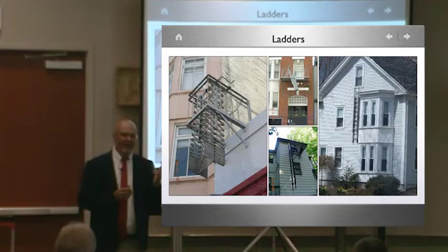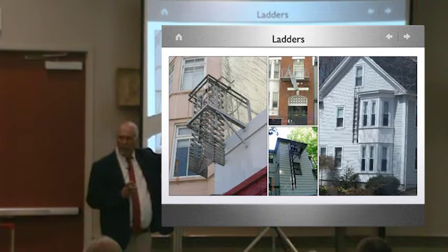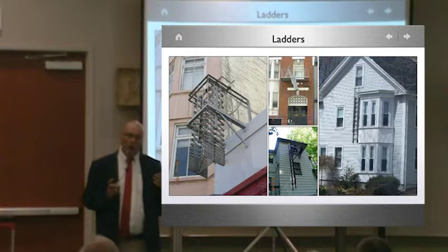Allowed, right? So here's the thing. You have to have a balcony outside your window so you can prepare yourself to use a ladder. These showed up on Saturday or Sunday, these ladders. Okay, guys? So my question always to the city official is, if you look in your files, there's no permit for this ladder. It was not built to code 75 years ago, and the homeowner installed this ladder. So in some cases, this triggers that I need a new egress stair, fire escape, which is usually 24, because that's the only place you're exiting is at that attic.